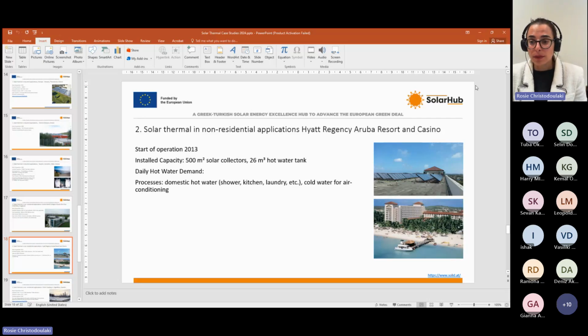So this is a big hotel. This solar thermal system consists of 500 square meters of flat plate solar thermal collectors, as we can see on the roof of the hotel. It also has a 26 cubic meter hot water tank. It is used for the hot water of the hotel residences, for showers, kitchen, laundry, and so on, as well as cold water for air conditioning.